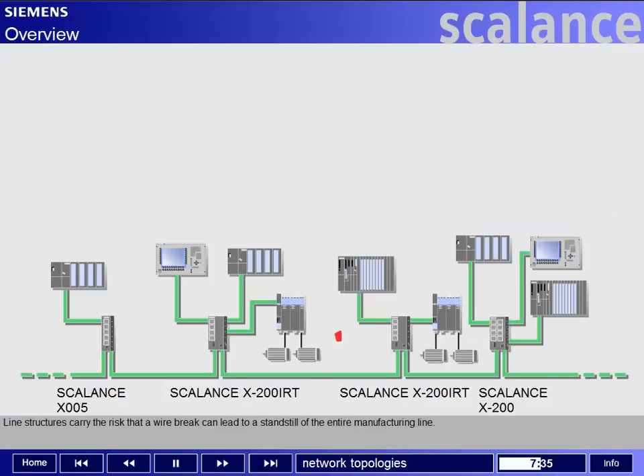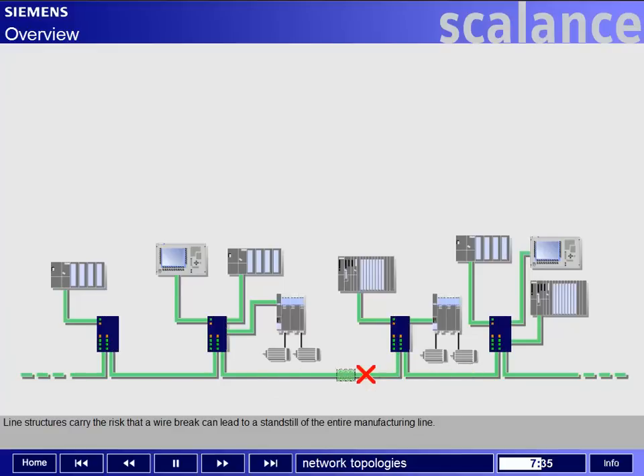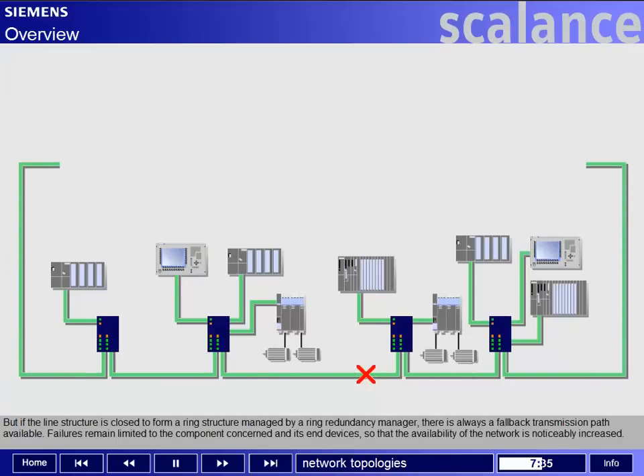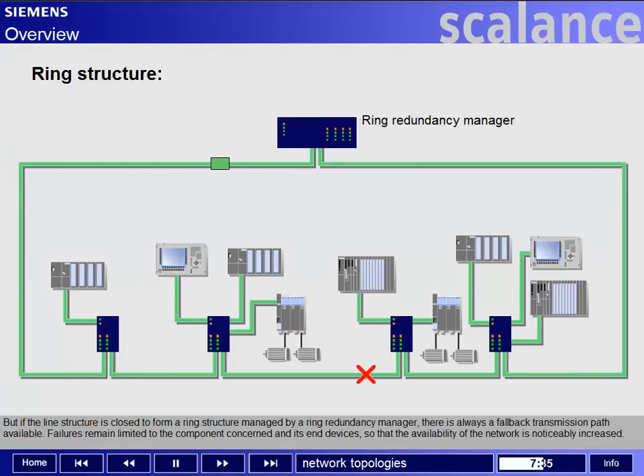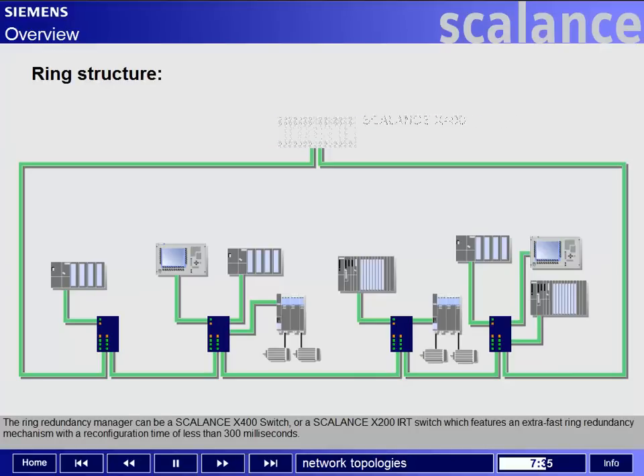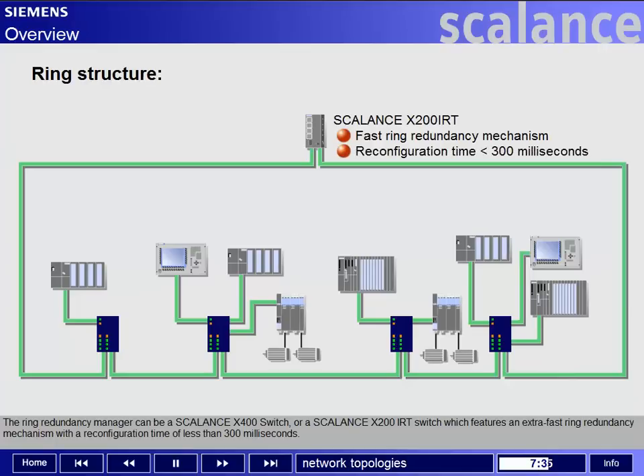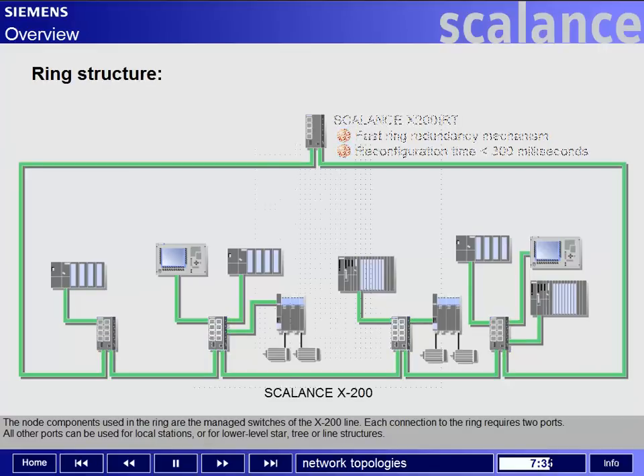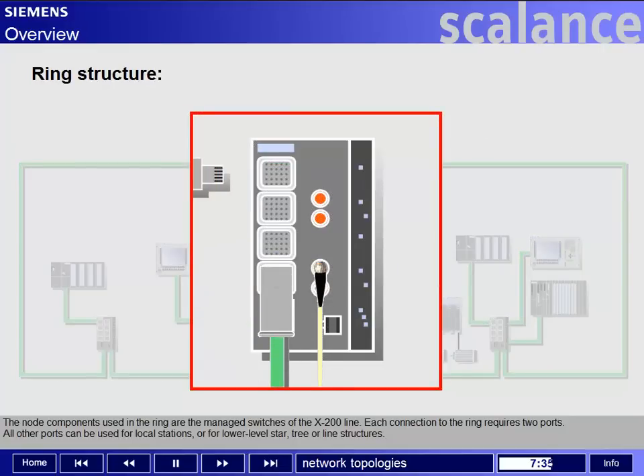Line structures carry the risk that a wire break can lead to a standstill of the entire manufacturing line. But if the line structure is closed to form a ring structure managed by a ring redundancy manager, there is always a fallback transmission path available. Failures remain limited to the component concerned and its end devices, so that the availability of the network is noticeably increased. The ring redundancy manager can be a Scalance X400 switch or a Scalance X200 IRT switch, which features an extra-fast ring redundancy mechanism with a reconfiguration time of less than 300 milliseconds. The node components used in the ring are the managed switches of the X200 line. Each connection to the ring requires two ports; all other ports can be used for local stations or for lower-level star, tree, or line structures.